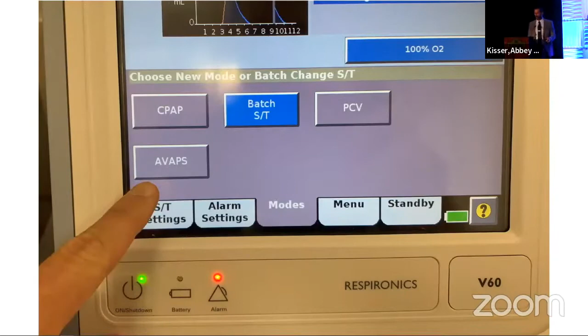So you click that little button and you see that you're able to select a tidal volume for your patient. Because one of the things about putting somebody on BiPAP is that you try to generate a certain tidal volume by increasing the IPAP. But here, instead of having a set IPAP on the device, you have a range. You see where it says min P and max P? That's your IPAP. You set the patient up on a range of pressure in order to achieve a certain tidal volume. So basically, it behaves like volume control on a ventilator. You set the volume, the machine chooses the pressure on every breath, and like that, you're able to oxygenate and ventilate your patient better.